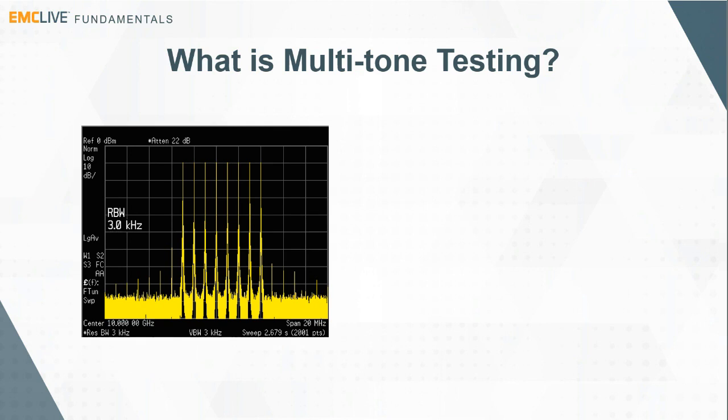Simultaneously controlling multiple signal sources and properly combining their output signals in a repeatable fashion is vital for accurately setting EMC test levels. AR has been a pioneer in this endeavor. With the release of EMCware 6.0, multiple tones injected into an amplifier can be corrected.